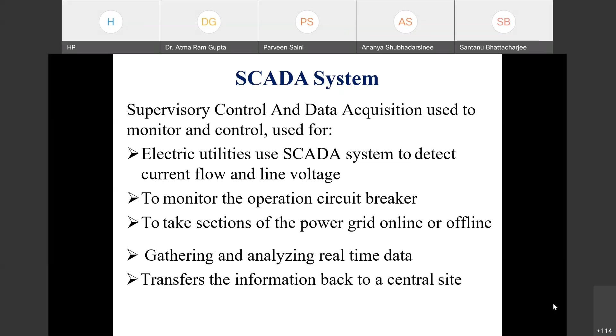Gathering and analyzing real-time data. Here the real-time data is captured in this system, and so we can make use of the storage or the gathering of that data, and afterwards we can analyze this real-time data. So in order to protect the system in anticipation, we can do the controls to avoid a major setback or major collapse of the system when some unnatural fault, a dip in the voltage, or some change in the frequency occurs. So that is also one of the big roles of the SCADA system, and it transfers the information back to the central site. So this supervisory control gathers and transfers this information, or feeds the information back to the centralized control station.